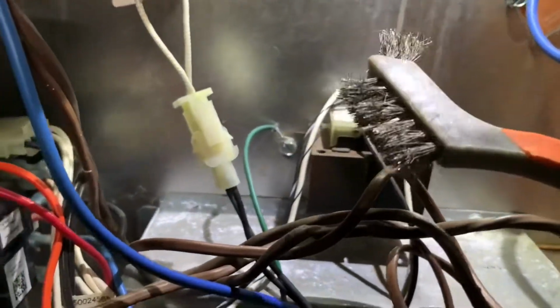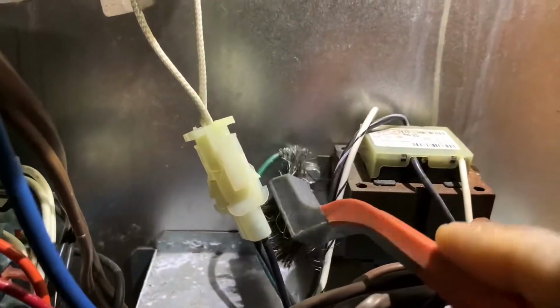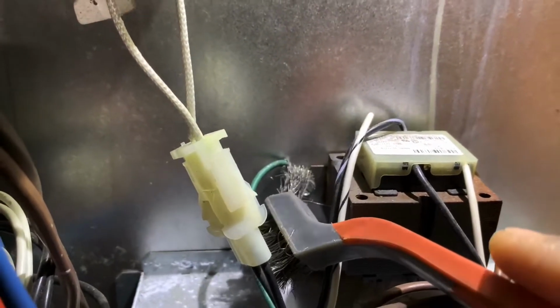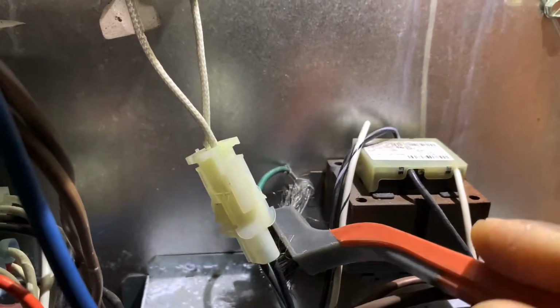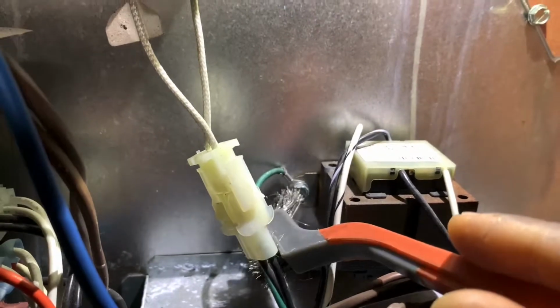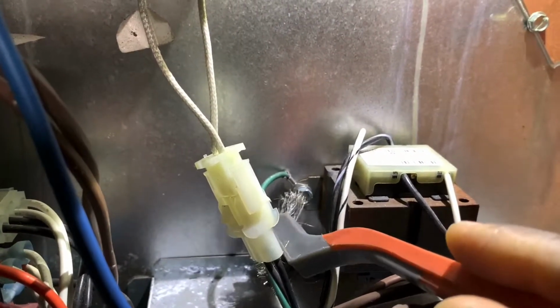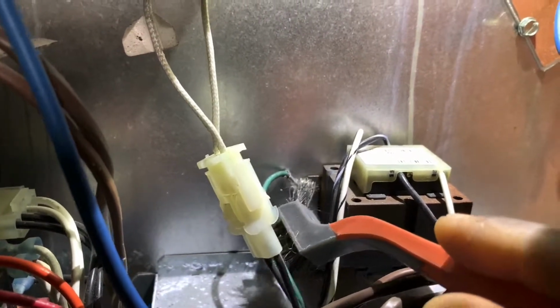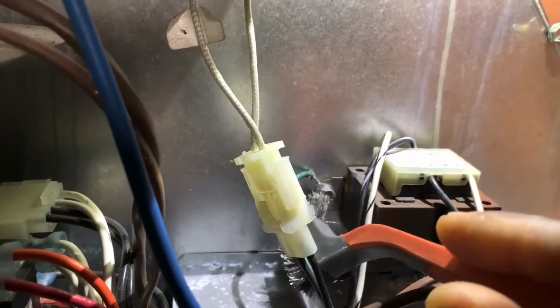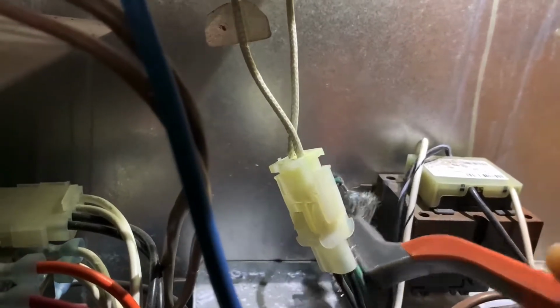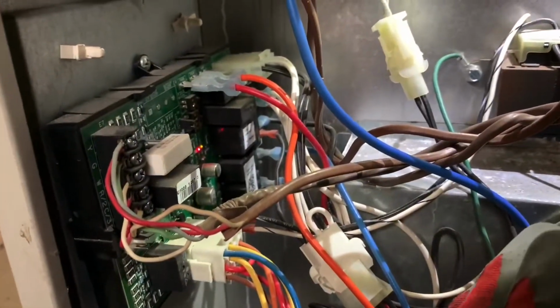You're going to have to make sure that you have a good ground connection, because you'll come on a service call for flame loss. The codes will be flame loss or loss of flame, and you replace or clean the flame sensor. But what most people won't do, they won't clean the ground connection, right? You see right here, that's the ground connection, right? So that's how the board is able to complete the flame sensing circuit. It has to go to ground.